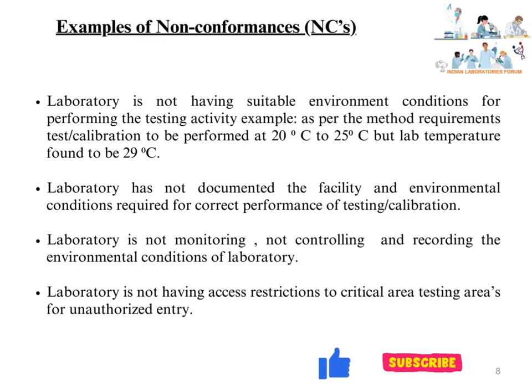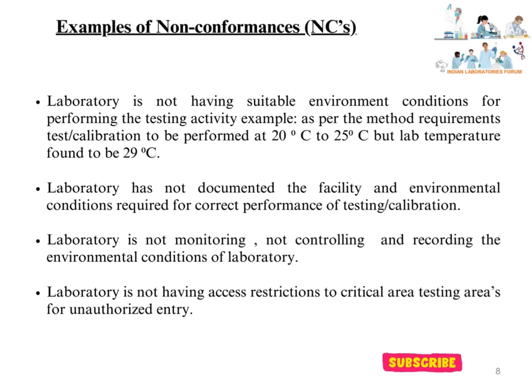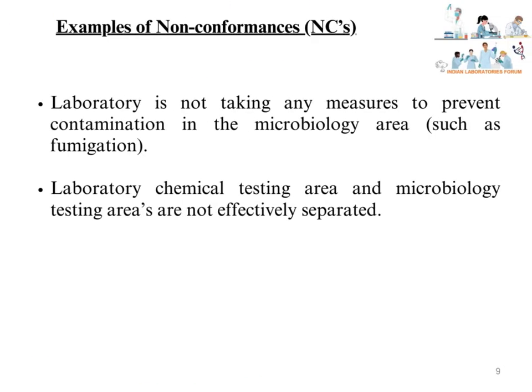Examples of non-conformances as per Clause 6.3: The laboratory is not having suitable environmental conditions for performing the testing activity — for example, the test or calibration is to be performed at 20°C to 25°C but lab temperature was found to be 29°C. The laboratory has not documented the facility and environmental conditions required for correct performance of testing or calibration. The laboratory is not monitoring, not controlling, and not recording environmental conditions. The laboratory is not having access restrictions to critical areas of testing or calibration for unauthorized entry. The laboratory is not taking any measures to prevent contamination in the microbiology area, such as fumigation. The laboratory chemical testing area and microbiology testing areas are not effectively separated.